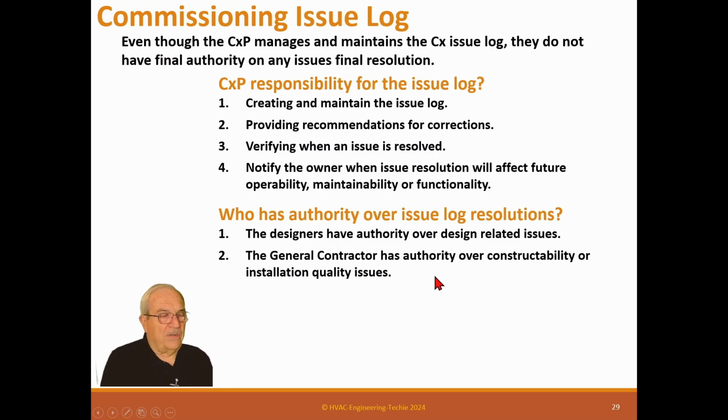Having been a contractor, poor quality drives me absolutely crazy. Because if you put up a system in the air, and you get there and look at it, and it's twisted and not level, and it looks terrible, I can't help myself. I have to take a picture. As a commissioner, you're not supposed to be judging quality, but I can't help it. Now, if quality is going to cause problems down the road, then you need to punch it.